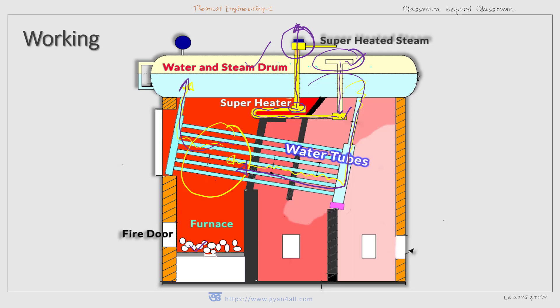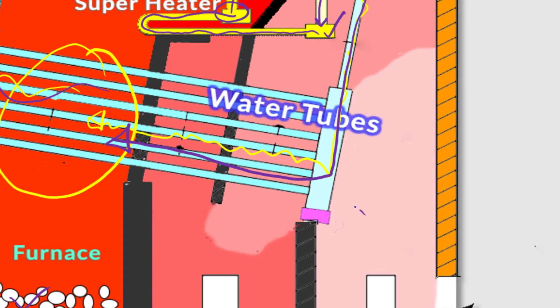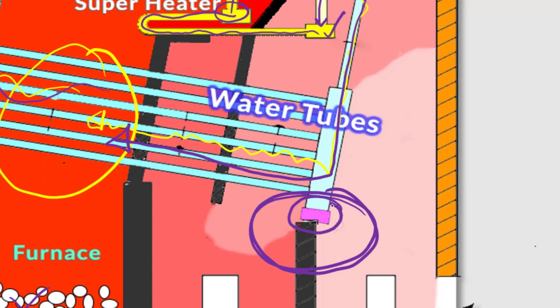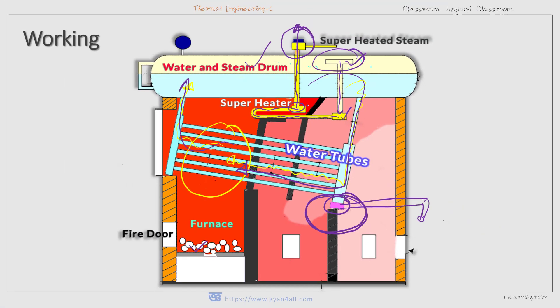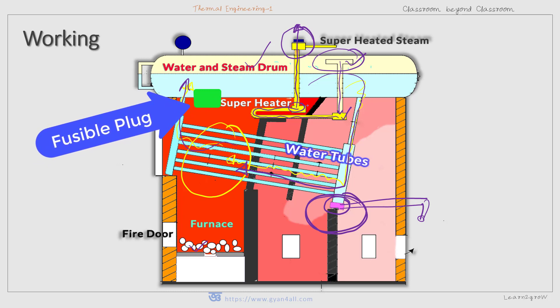At the lowest point of the boiler, mud and sediments are collected in the mud box and blown out through the blow-off cock periodically. All mountings — including the steam stop valve, safety valve, water gauge, pressure gauge, feed check valve, and fusible plug — are attached to the boiler for safe operation.